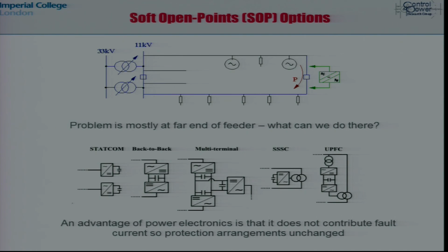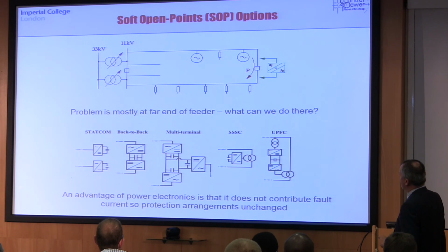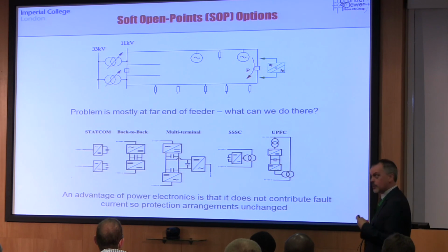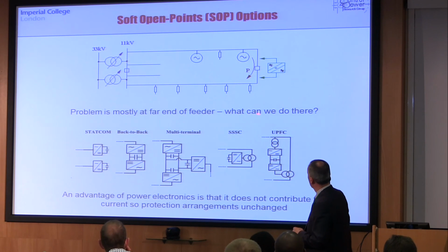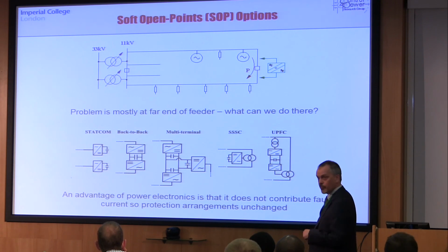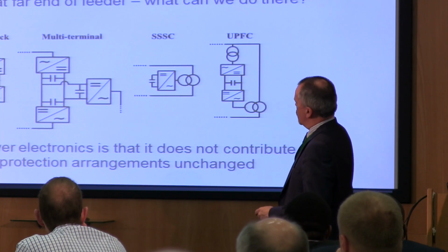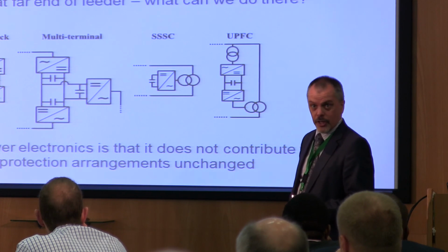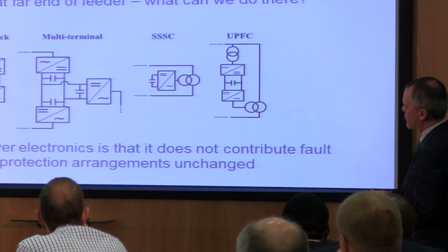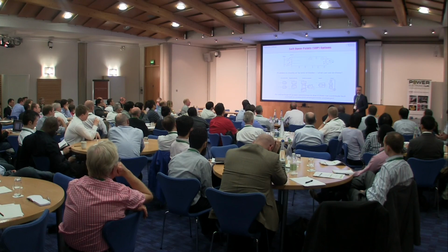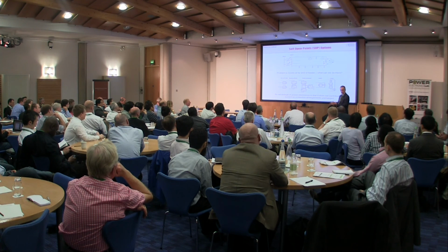So it pushes us towards using stuff at the far ends of the feeders where you see the biggest voltage variation, where normally, this poor choice of word, practice is to have an open point, a switch one could close to provide an alternative route to supply a feeder if there's a fault further up the feeder. So that point normally runs open, but we have the two ends of the two feeders available to us, and we can do something with some power electronics, which is what we've come to call the soft open point. This is an open point, and this makes it soft by allowing some power transfer. Well, if I put back-to-back converters there, I get power transfer between the feeders, and I can pull a bit of power off the generation-rich feeder and push it onto the load-rich feeder and even up the feeder use and bring the voltages back into alignment.